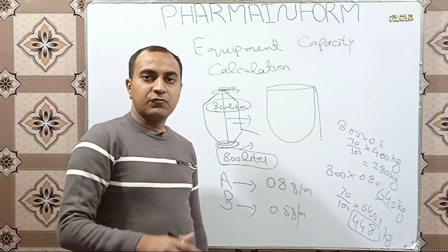So the next question is how we can calculate the quantity of water which is filled into any blender. For this you can use flow meters. By using a transfer pipe attached with a flow meter, you can easily calculate the volume of water filled into the blender. And if you do not have a flow meter, simply you can use a measured or calibrated container, suppose a 50 kg container, add it into the blender and count the number of containers added into the double cone blender.